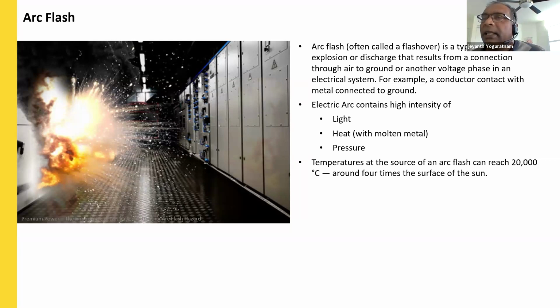When it comes to arc flash, there are a few parameters we need to understand. One is the arc flash boundary. Arc flash boundary is the term used to describe the distance at which a person without personal protective equipment may get a second-degree burn if an arc flash occurs. From experiments, it has been found that if a point has an incident energy of 1.2 cal per centimeter squared, a human being can be exposed to a second-degree burn.